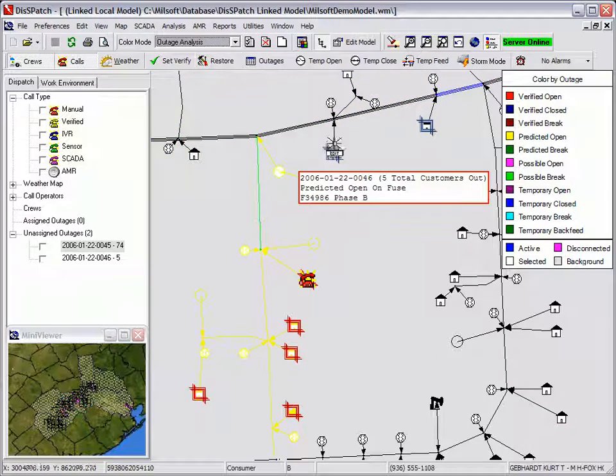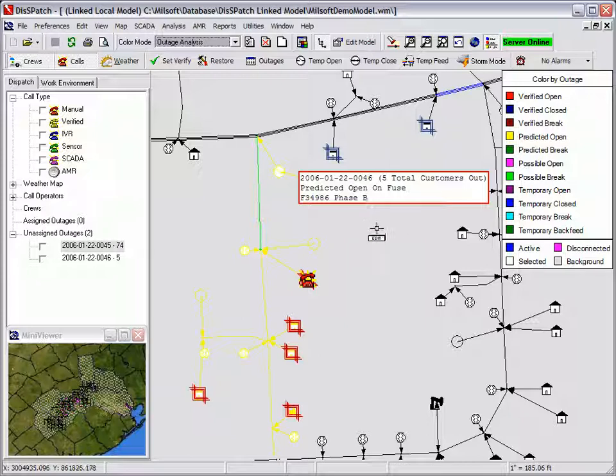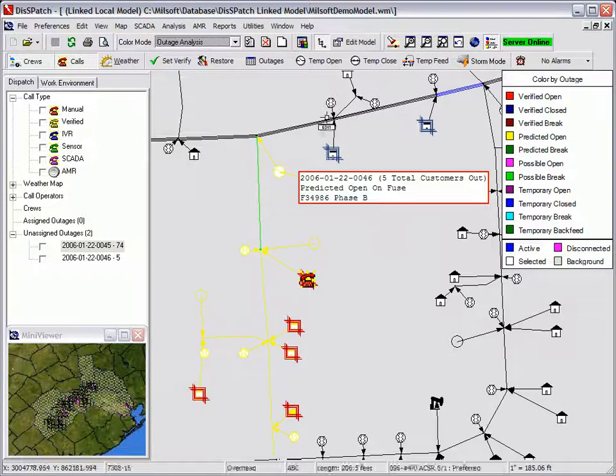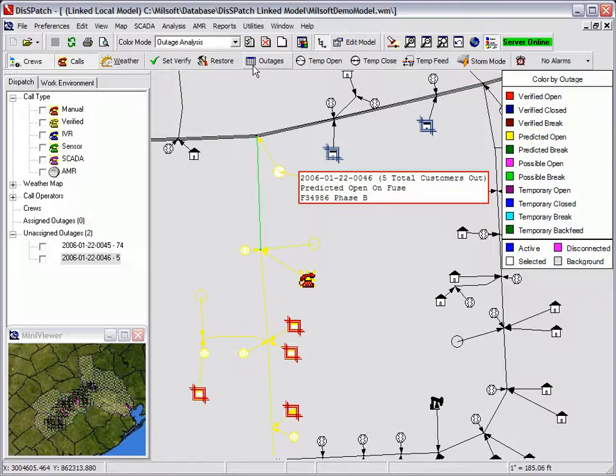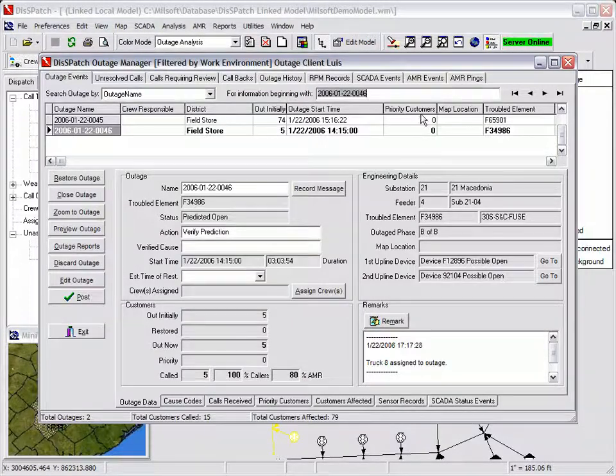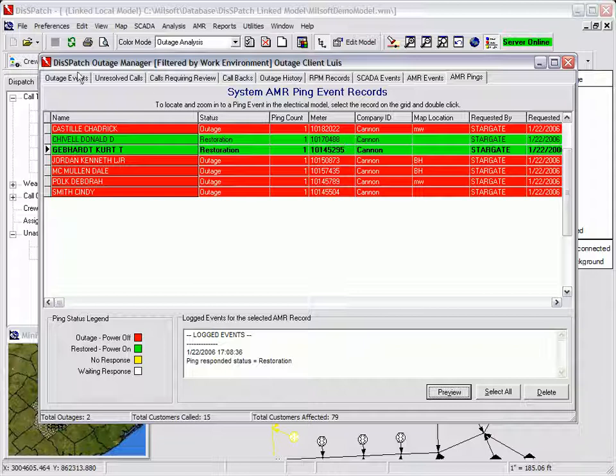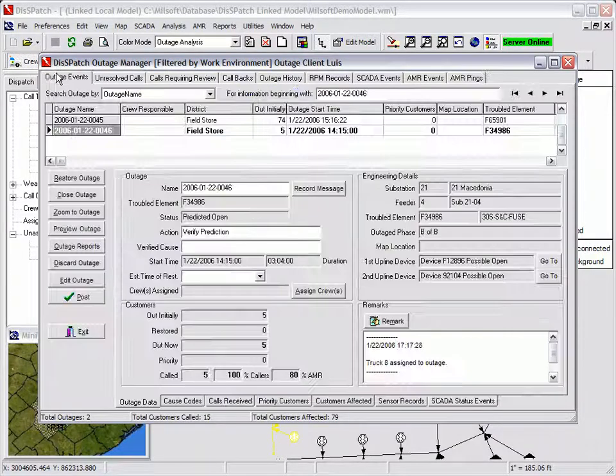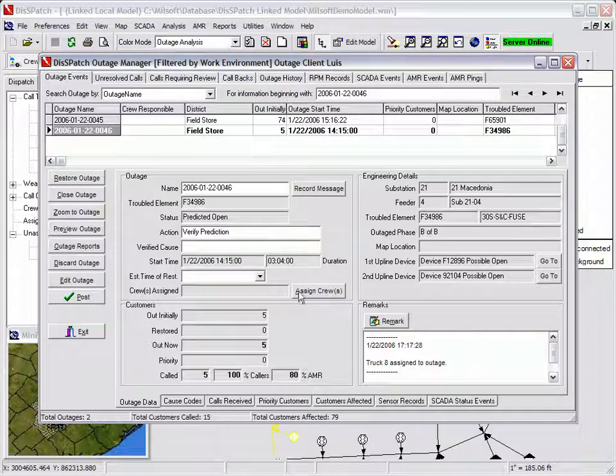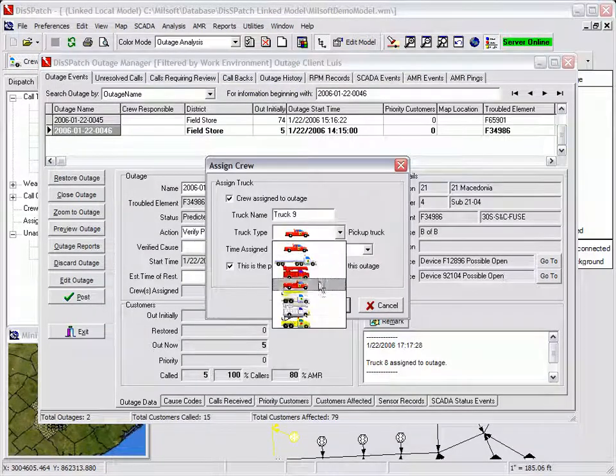The dispatcher notices that the two upline AMR meters have reported that they have power. This is confirmed by the two AMR icons changing back to the normal on state and by the AMR records in the outage manager. The dispatcher then dispatches a crew to the reported fuse outage.